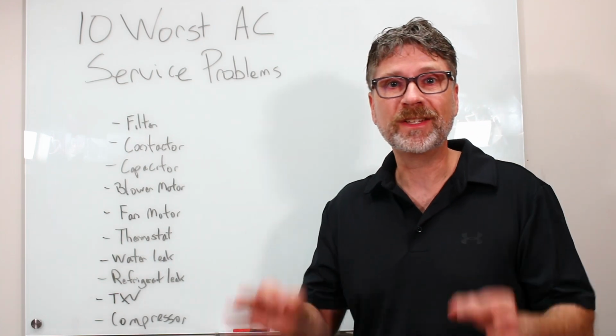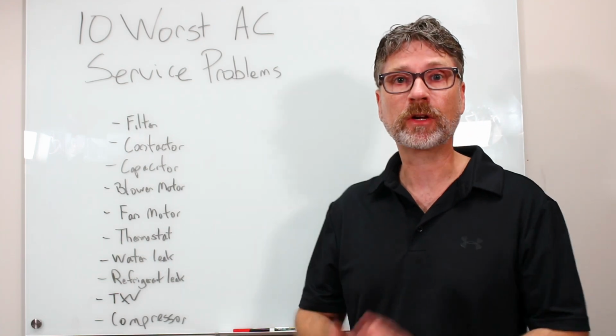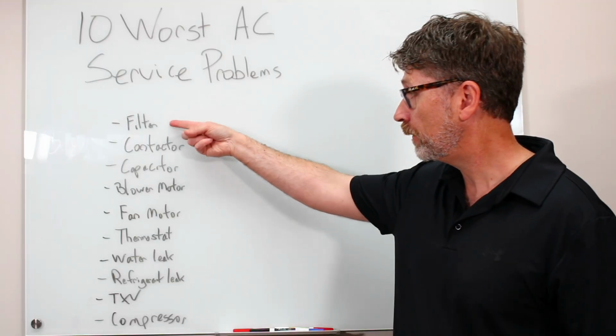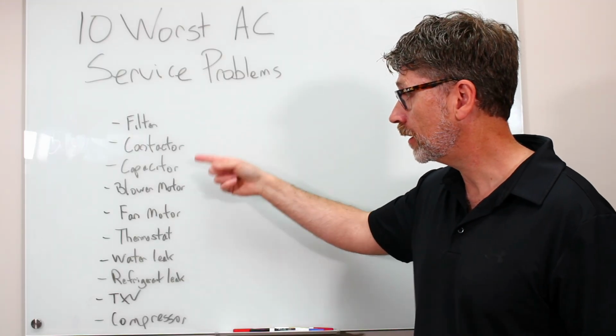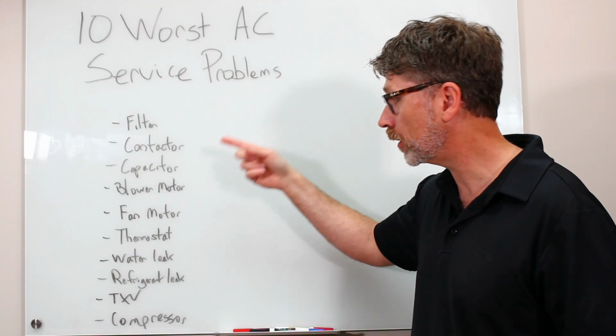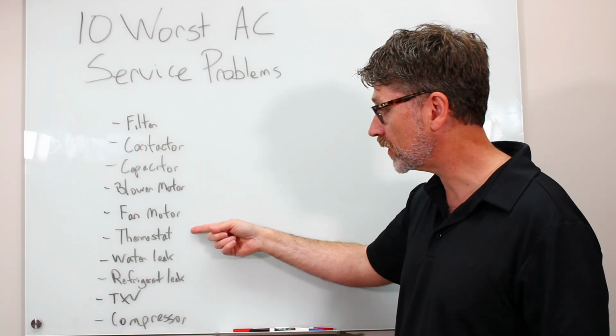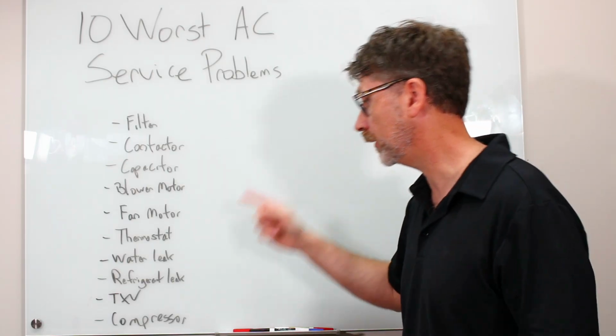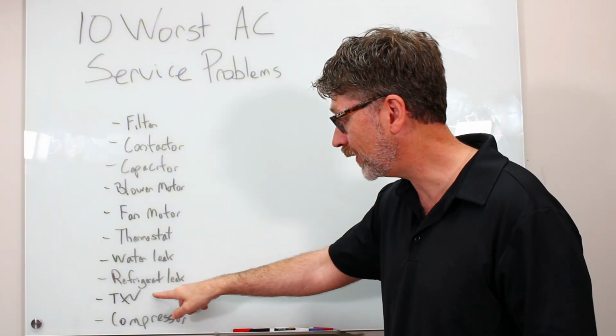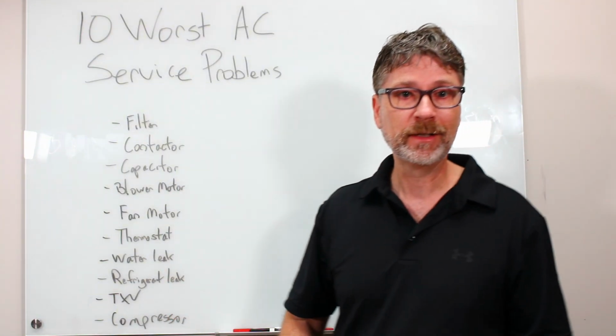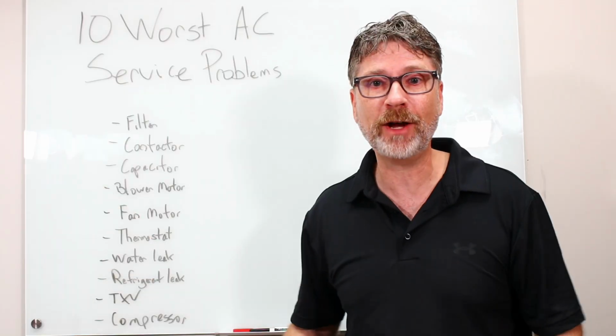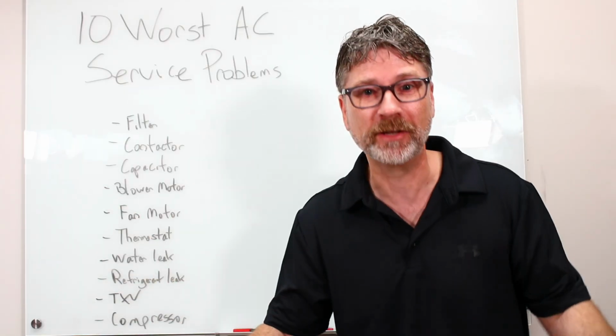So here's the list of the top 10 AC or heat pump service problems. Filters, contactors, capacitors, blower motor, fan motor, thermostat, water leaks, refrigerant leaks, TXVs, and the compressor. Avoid all of these and your system could last forever. Just kidding. Nothing's really forever.